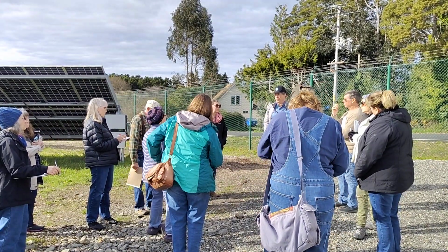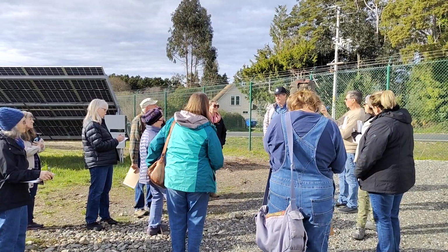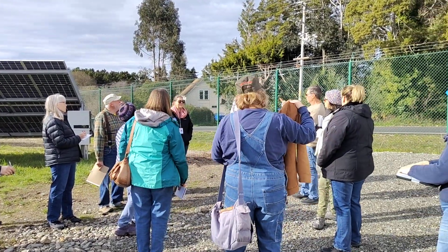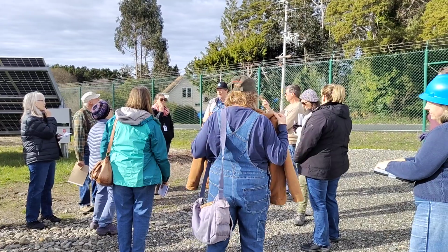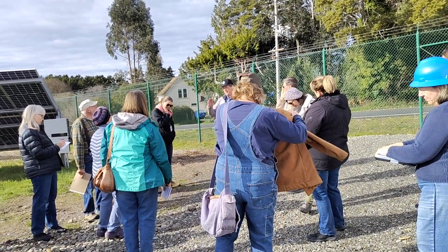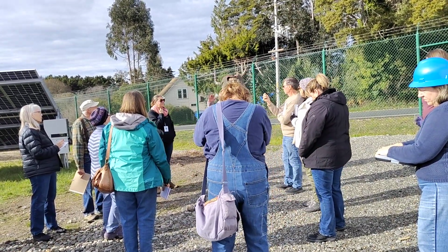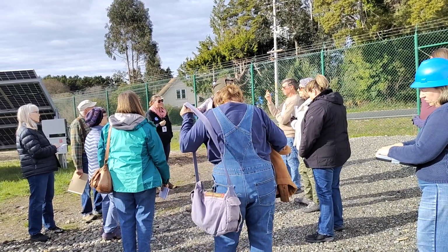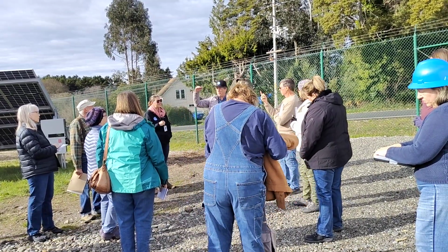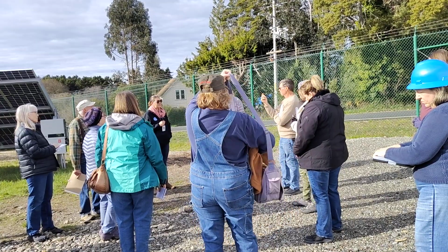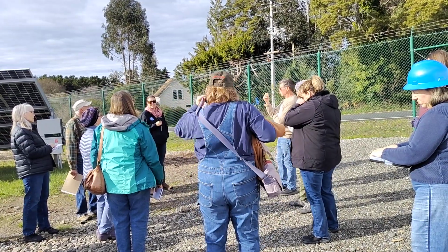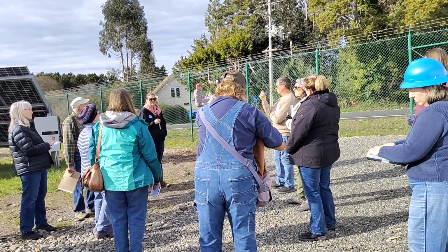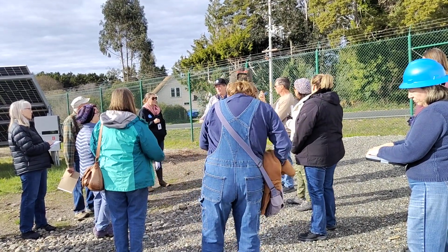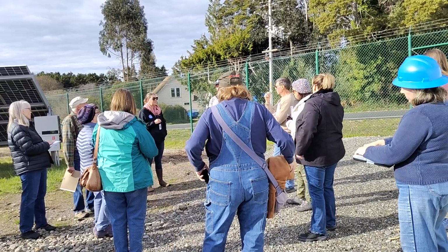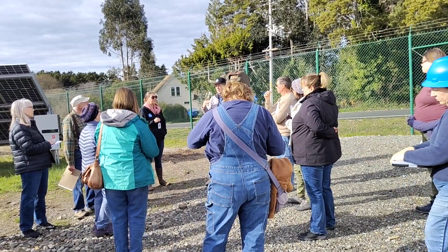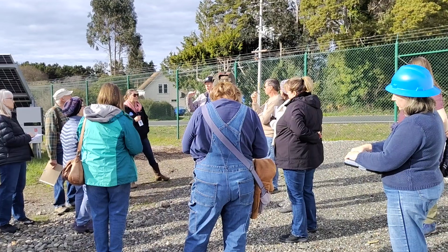We'll never do that because we never want to draw the battery all the way down, for two reasons. One, it's not healthy for them. They have design limits, so you have to talk about state of charge, how low and how high you're willing to go. We won't drop it below 20% because of the technology of these batteries, and we don't like to go above 96%. But in fact, we actually reserve about 40%. And if we have a storm mode where we think a storm's coming on, then we'll reserve the whole battery capacity.